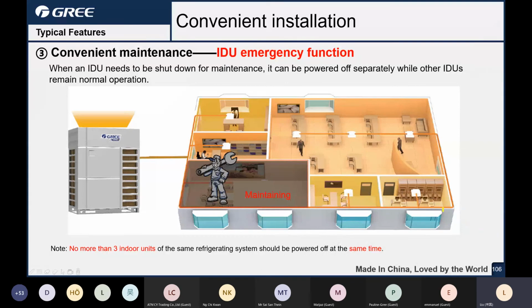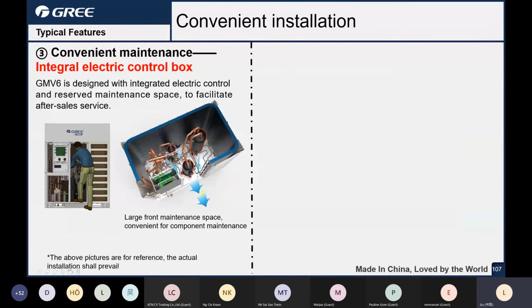And for indoor unit emergency, if some indoor units are offline or have a problem, you can disconnect the indoor units from the network. No more than 3 indoor units can be removed from the system at the same time. Okay, that's good for the total system running, even if you have some indoor units to troubleshoot. Okay, no more than 3 indoor units. That's the emergency for the indoor side.